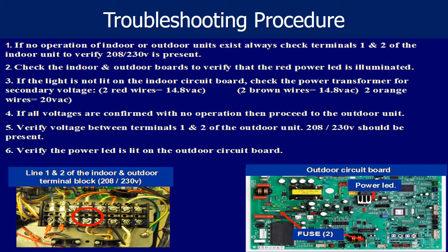at the outdoor unit and the indoor unit's power supply terminals 1 and 2. Also, verify the fuses on the indoor and outdoor unit's main control boards are good. If the boards are being powered properly, there will be a solid LED lit on the control boards. Also, check for the error codes on either the indoor or outdoor unit.